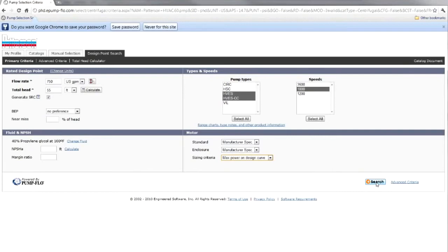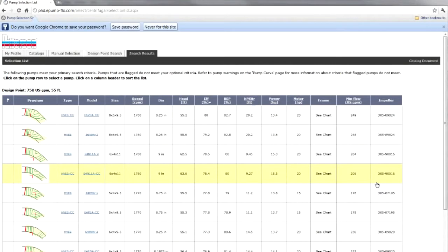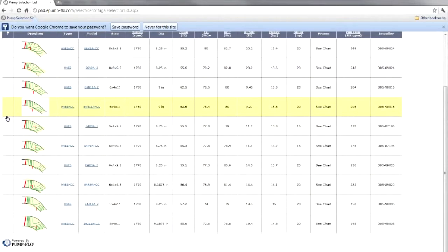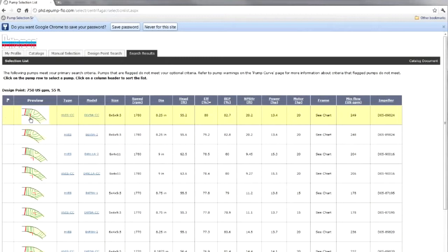So now we click the search button. Now this is a beautiful, beautiful screen here, because this gives us a bird's eye view of what we look like on our curves. And you can see where our operating point falls with that first pump, that E6V9A. That is going to be a little bit to the left of best efficiency point. Now it looks like we're probably within that 66% of best efficiency point, so that could be a good pump. Typically this will start with sorting based on the efficiencies. So you'll notice the first pump up is 80% efficient, and as we drop down the list, the efficiencies also drop.